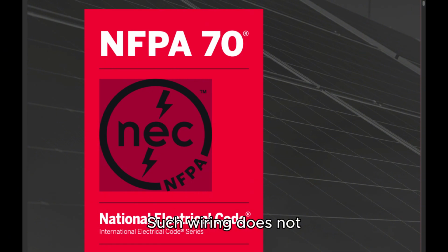Such wiring does not include wiring internal to appliances, luminaires, motors, controllers, motor control centers, and similar equipment. CMP1 Informational Note: Power sources include, but are not limited to, interconnected or standalone batteries, solar photovoltaic systems, other distributed generation systems, or generators.